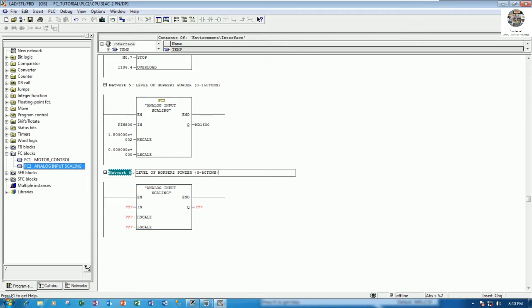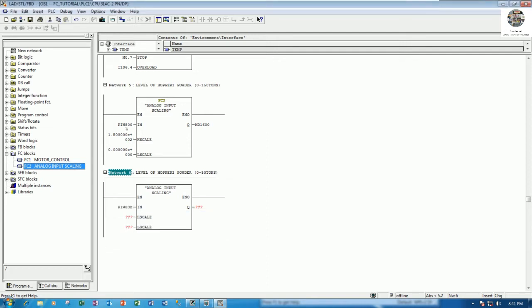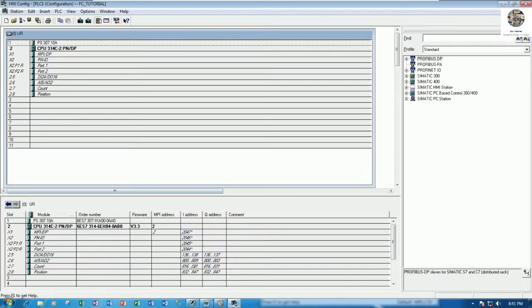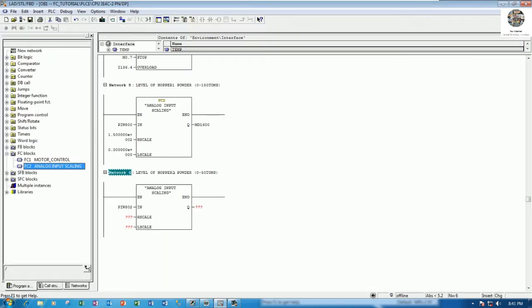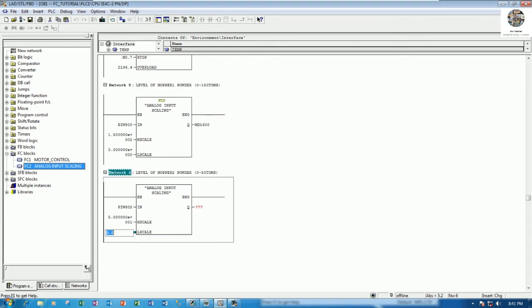I will start from PIW 802, because it is the integer. To compare with our hardware configuration — 800, 802, 803, 804, 805, 806 up to 809. The range is 0 to 50 tons, so 50.0 and 0.0, and here is the output real.